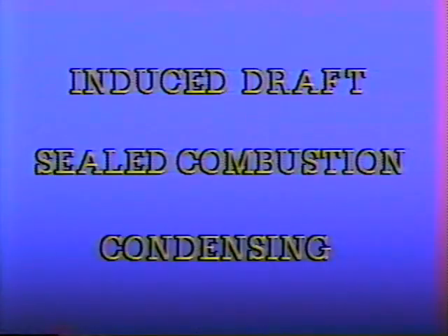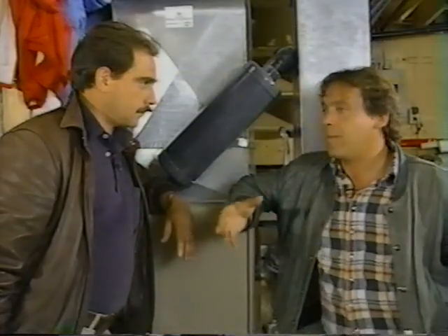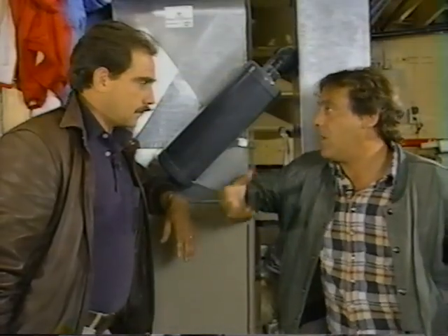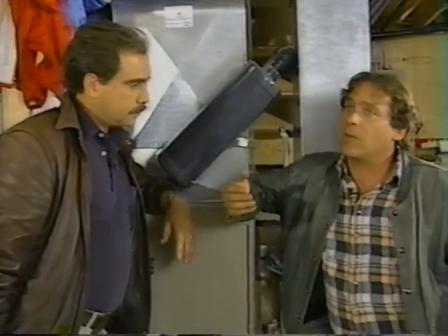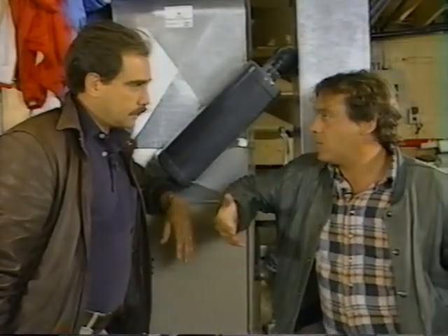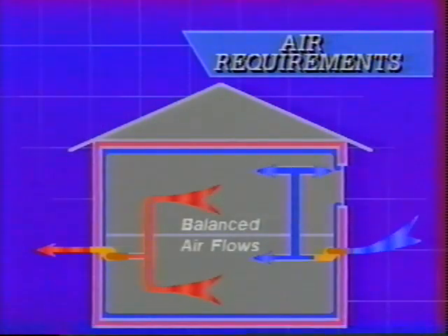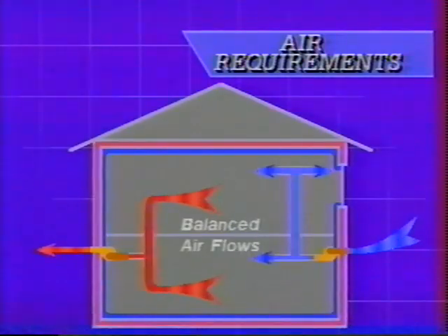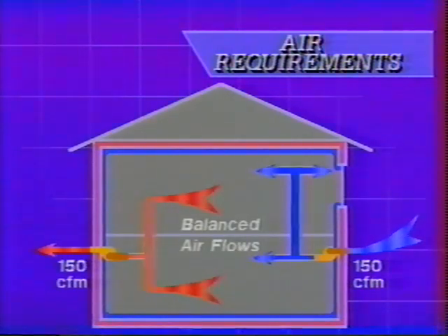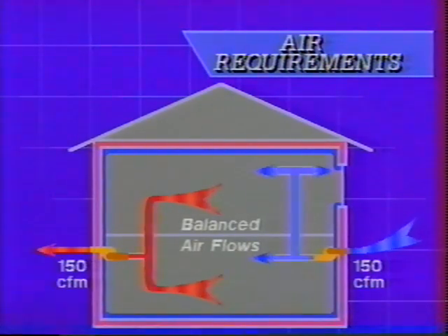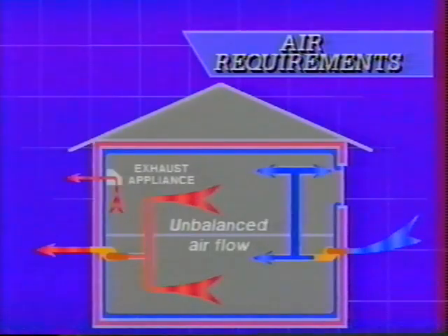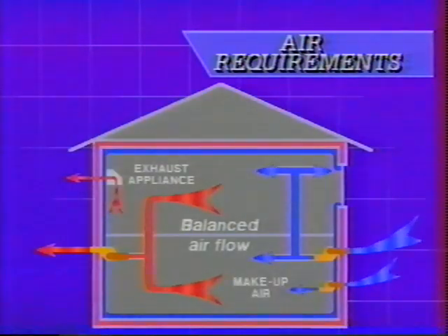Right, and my old monster in the basement doesn't require anything like that because most conventional houses are so leaky, but we're airtight. Now, can you rely on the mechanical ventilation system to supply air for combustion? Adamantly not. If you think back to our last program, I think you'll remember why. The mechanical ventilation system has to have balanced airflows. If we're supplying 150 cubic feet per minute to the house, we have to be exhausting 150 cubic feet per minute. Right. Other exhaust requirements, air needed for combustion appliances, barbecue ranges, anything like that will have to be provided in another manner.